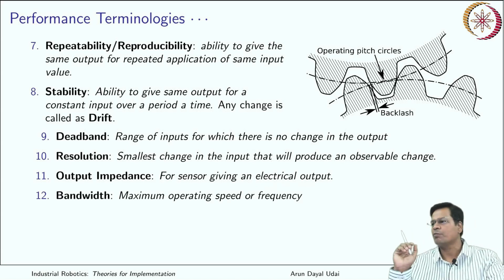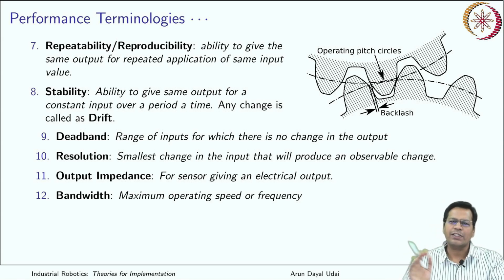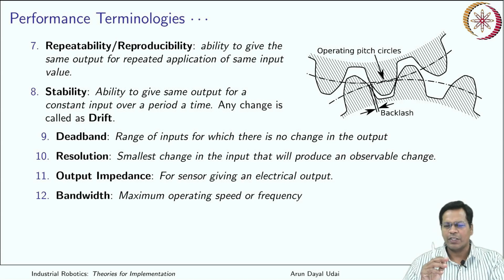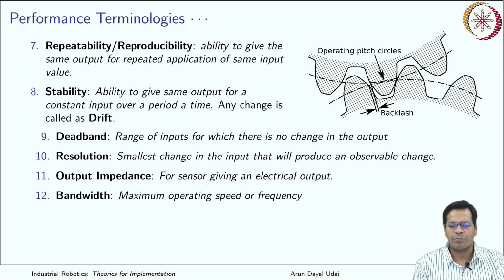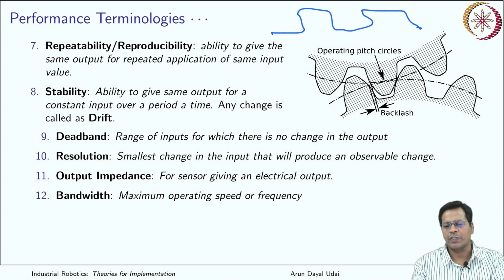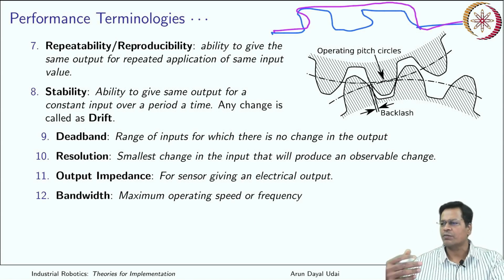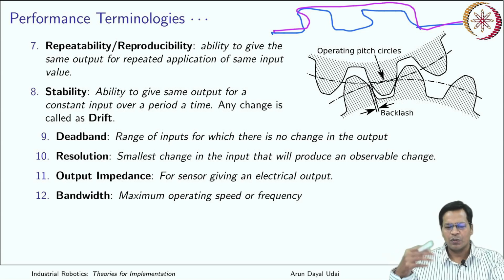Bandwidth is the maximum operating frequency, how fast your device can change; that is also very important. You have seen this in the case of a proximity sensor: if the switching goes beyond 20 kilohertz, off and on, it behaves as if it is totally on all the time. Instead of giving off and on, it gives a uniform, constantly-on signal. So beyond a certain frequency, it gives bad results and does not switch off properly. There are devices with different frequency ratings that must be selected carefully before implementing in an application.